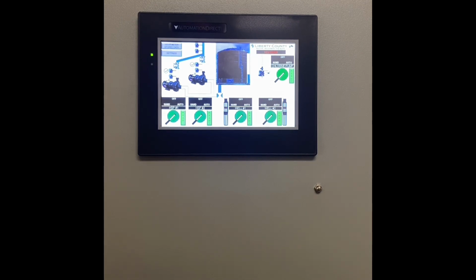Acknowledge merely turns off the light outside for the alarm. It keeps that pump in a failed state, and it allows the other pump to take up and run as the lead well or the lead service pump, respectively. If you hit reset without fixing the cause, it will fail again and you will be chasing your tail in a vicious circle. So press acknowledge, find and correct the cause, then press reset. Once you press reset, the failed indication, the reset, and the acknowledge buttons will be hidden away again. The high service pumps have a very similar failure, and they will also pop up over top of the motors with the same acknowledge and reset buttons.